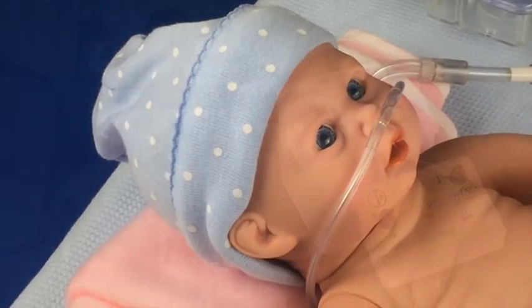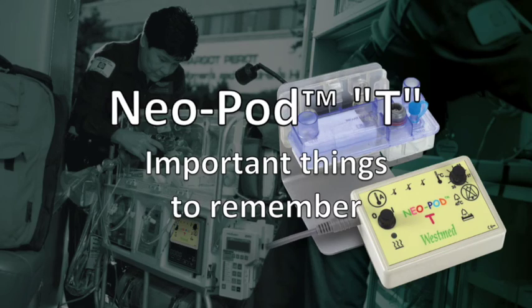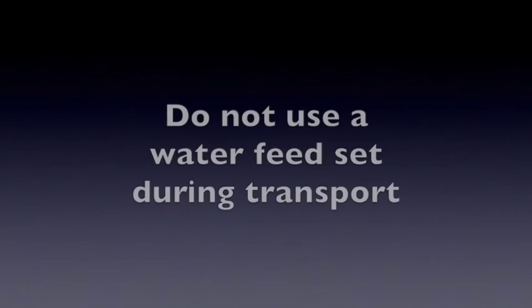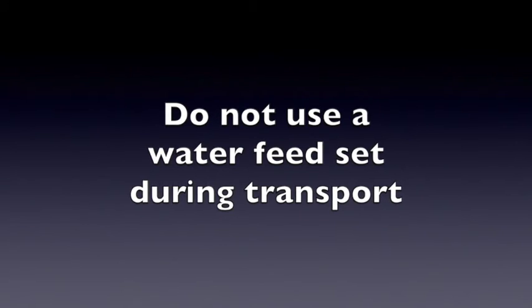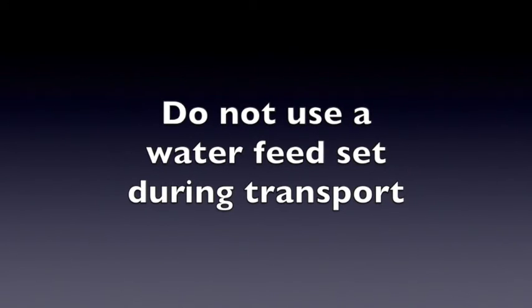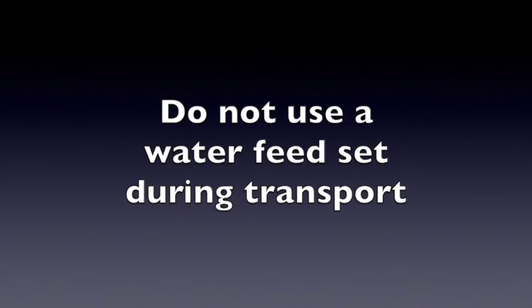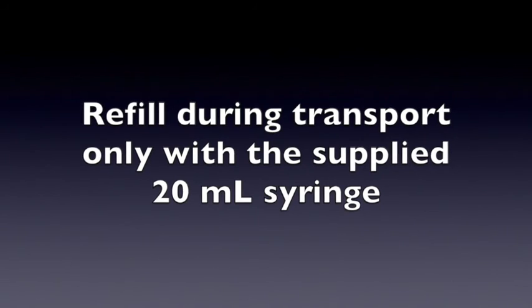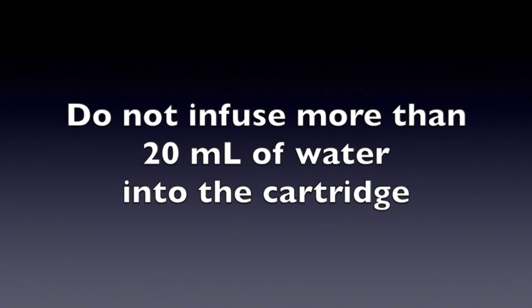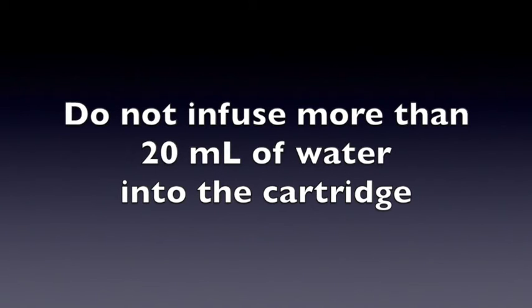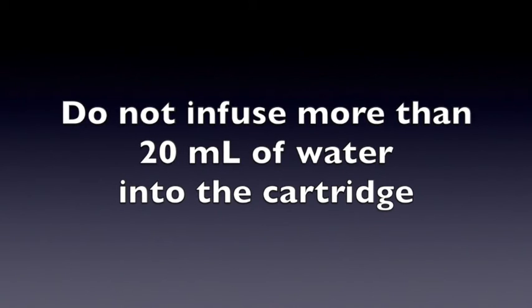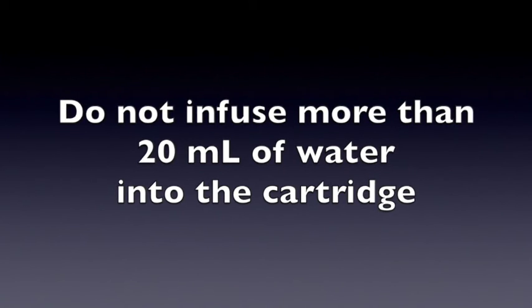When using the Neopod T, it is important to remember: do not use a water feed set during transport. Motion or conditions that are not level can cause the LavaBed cartridge water level float to malfunction. If additional water is required during transport, supply only with a syringe. To prevent excess water from entering the patient airway, the LavaBed cartridge incorporates a safety drain. If an excessive amount of water is applied to the LavaBed cartridge, the safety drain opens and drains excess water out the bottom of the cartridge. When filling the LavaBed cartridge initially, do not infuse more than 20 milliliters of water into the cartridge on setup.